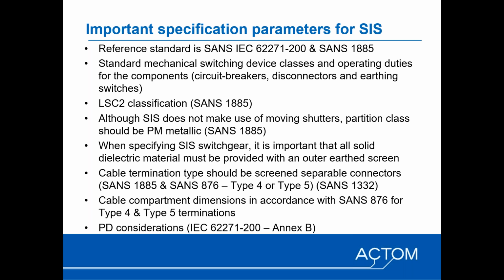So they still incorporate mechanical switching devices, and the classes would be the same as for AIS and GIS. So your mechanical endurance, your electrical endurance, the capacitive switching performance, the application classes S1 and S2, all of those remain the same, nothing special in that regard. And so it's just important to bear that in mind. Loss of service continuity: because it's fixed pattern, it's important to bear in mind that only LSC2 is effectively applicable. That's because you have one accessible high voltage compartment, and that's the highest level that is available for a fixed pattern architecture.